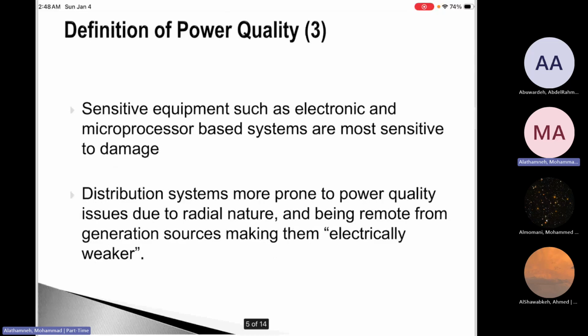Now, the next thing: sensitive equipment. Sensitive loads and weak disturbance. There are two key messages here. The first is that sensitive equipment, microprocessor-based equipment, is not forgiving. Basically, it needs a stable voltage and a clean waveform. Any small dip that a motor would ignore can crash a PLC or a server. That can create a big problem, which makes it very sensitive, as I said, microprocessor-based equipment is very sensitive.